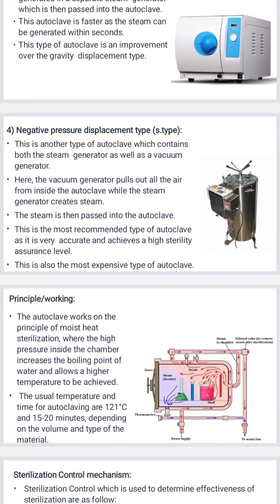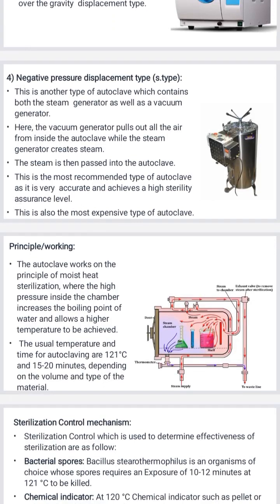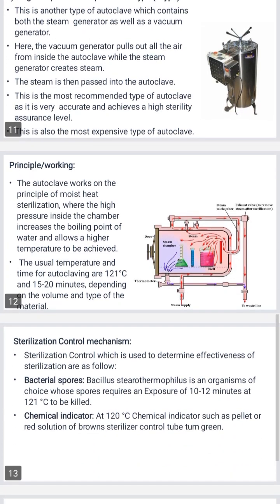Principle and working. The autoclave works on the principle of moist heat sterilization, where the heat and pressure inside the chamber increase the boiling point of the water and allow a higher temperature to be achieved. The usual temperature and time for an autoclave are 121 centigrade and 15 to 20 minutes, depending on the volume and the type of the material.